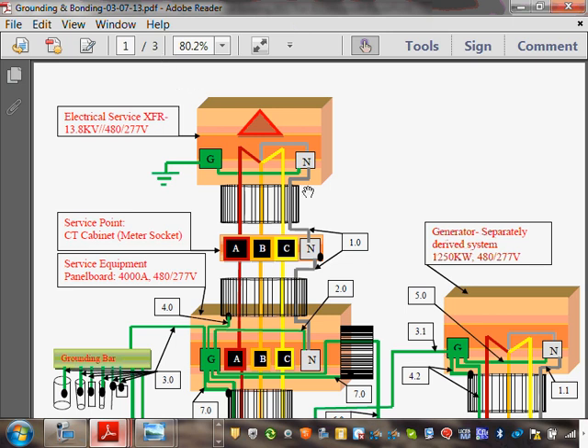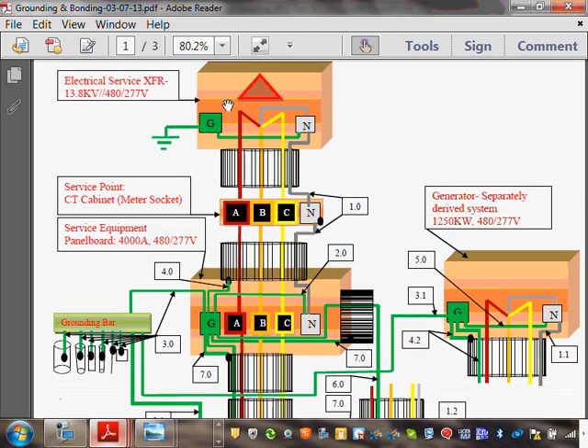Okay, so if you start with the sheet, guys, it has three things. First of all, when I put the sheet together, I wanted to put all the grounding and bonding in one big sheet, just one page. I don't want to spread it over multiple pages. That's why it's kind of more involved. So right on the sheet, you're looking at a grounded system. You're looking at a switch. Here's my transformer. That's a solidly grounded transformer. You can see here I'm bringing the three-phase. I took the worst scenario, which is a 4,000 amp, 480/277 system. That's as bad as you can get.